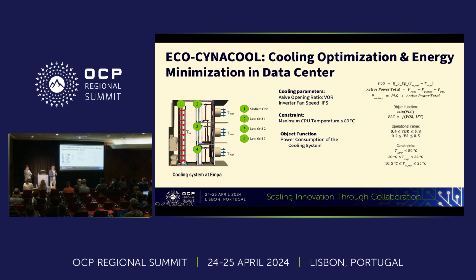We have to minimize the power consumption of the cooling system by optimizing fan speed and valve opening ratio, which adjusts the flow rate through the heat exchanger, since heat is removed from air using this heat exchanger. We need to reduce the heat load sent to the chiller, located outside the building.